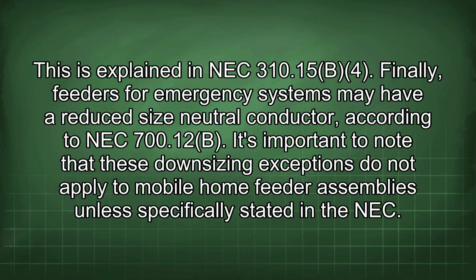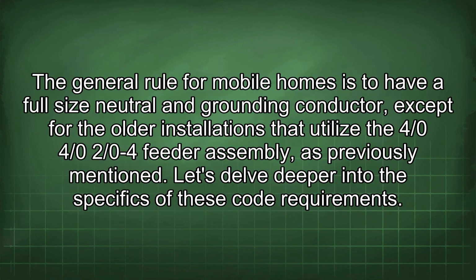It's important to note that these downsizing exceptions do not apply to mobile home feeder assemblies unless specifically stated in the NEC. The general rule for mobile homes is to have a full-size neutral and grounding conductor, except for the older installations that utilize the 4/0-4/0-2/0-4 feeder assembly, as previously mentioned. Let's delve deeper into the specifics of these code requirements.